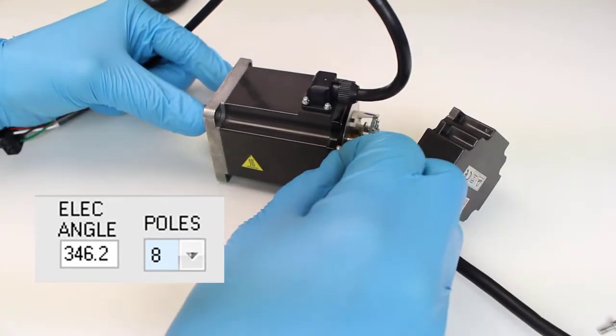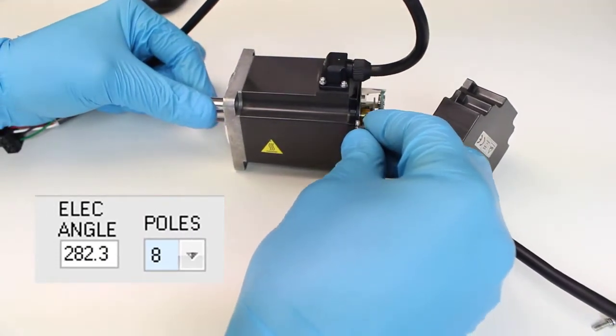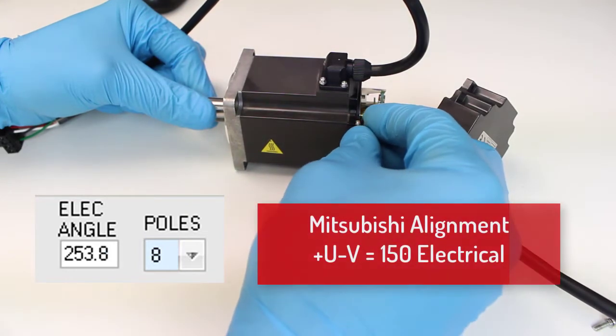Lock the motor with plus U minus V and set the angle to Mitsubishi's standard of 150 electrical degrees. Then tighten the first set screw.